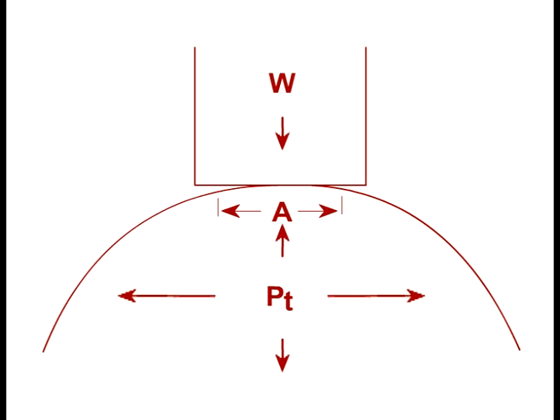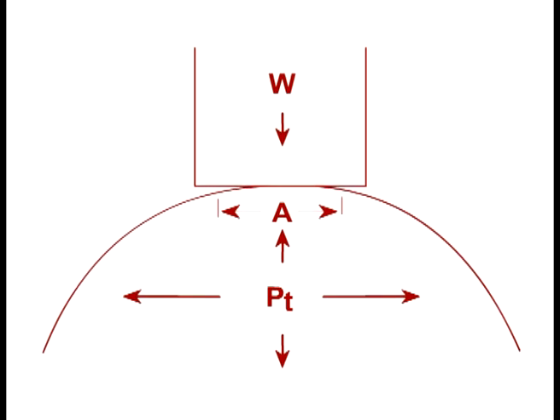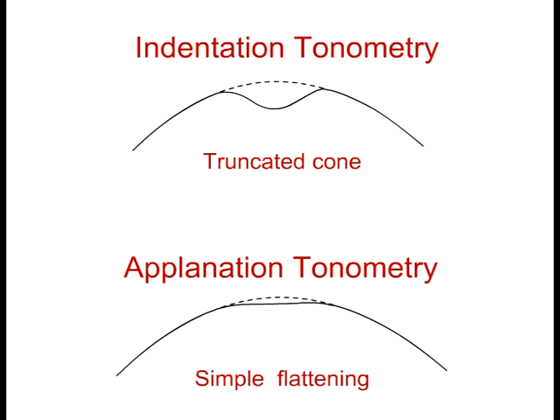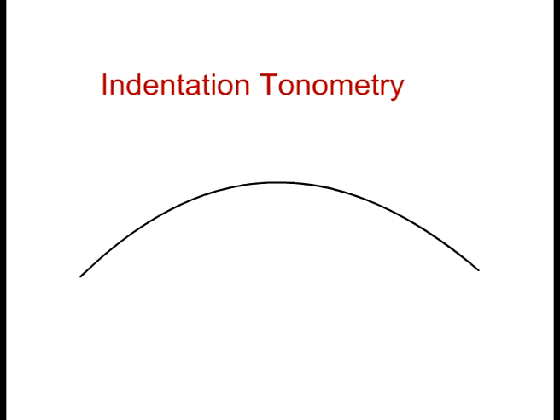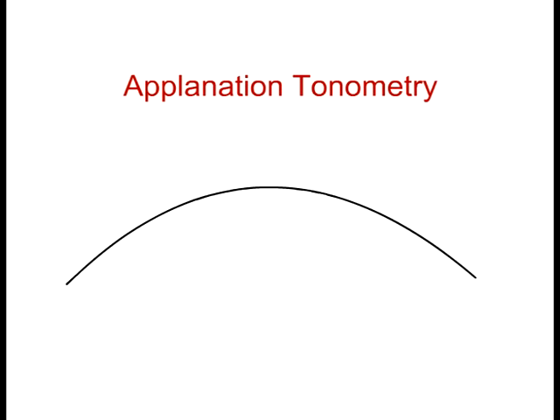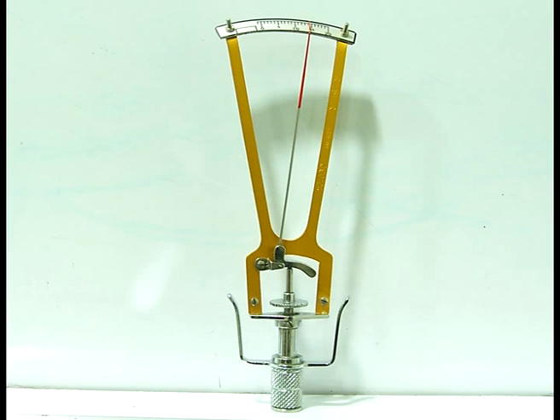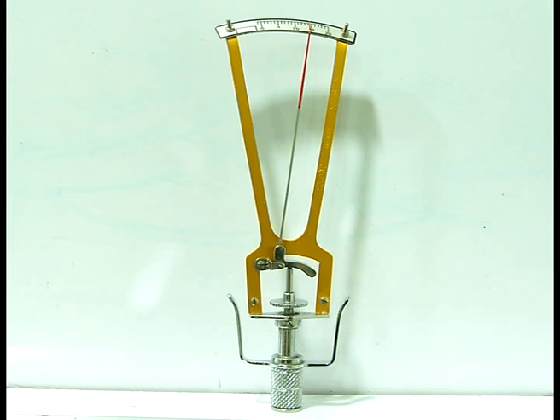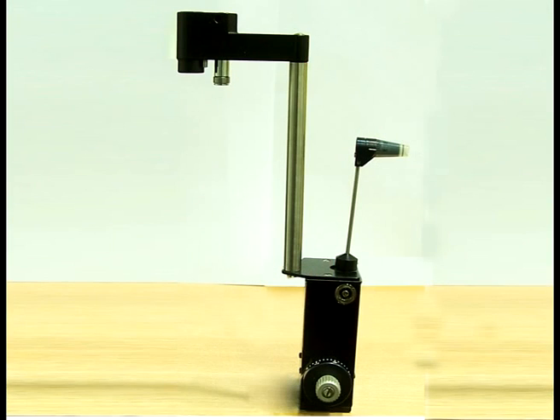Intraocular pressure is measured by relating deformation of the globe to the force responsible for deformation. Depending on shape of deformation, tonometry has been categorized into two types: indentation tonometry, where the shape of deformation is a truncated cone, and applanation tonometry, where the shape of deformation is simple flattening. Their prototypes are Schiotz's tonometer and Goldman aplanation tonometer respectively.